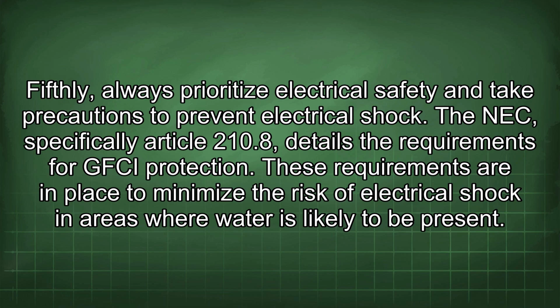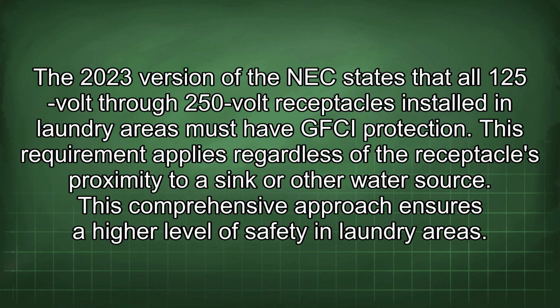These requirements are in place to minimize the risk of electrical shock in areas where water is likely to be present. The 2023 version of the NEC states that all 125-volt through 250-volt receptacles installed in laundry areas must have GFCI protection. This requirement applies regardless of the receptacle's proximity to a sink or other water source. This comprehensive approach ensures a higher level of safety in laundry areas.